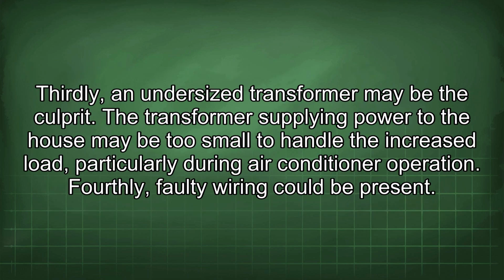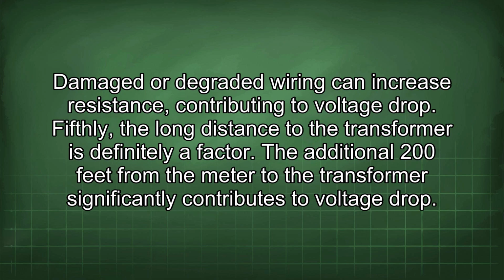Thirdly, an undersized transformer may be the culprit. The transformer supplying power to the house may be too small to handle the increased load, particularly during air conditioner operation. Fourthly, faulty wiring could be present. Damaged or degraded wiring can increase resistance, contributing to voltage drop.